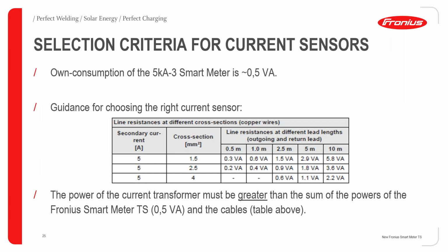What is the selection criteria for our current sensors? We do not have any direct recommendation of any brands of current sensors to use, but we do have one recommendation on the selection criteria. Remember, the power of the current transformer must always be greater than the sum of the power of the Fronius Smart Meter and the cables.